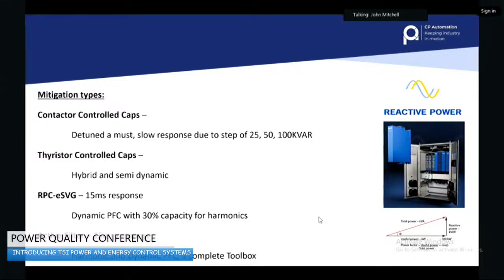So what can happen is you can get a resonance, and when that resonance occurs, things start failing: the capacitors burn out, the drives fail. Again, having a Sine Tamer on the panel to protect the drives is a really good idea, especially if you don't know what else is installed in the plant.